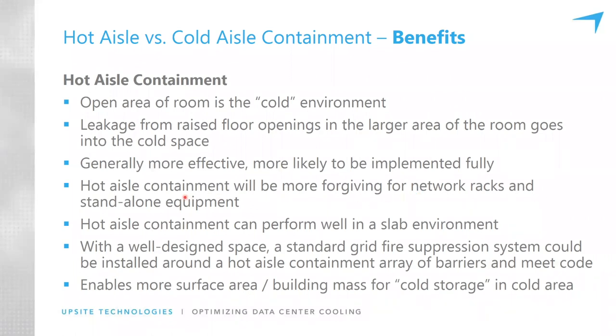Hot aisle containment can perform well in a slab environment. And with a well-designed space, a standard grid fire suppression system can be used and installed around a hot aisle containment and still meet code. This enables more surface area and building mass for cold storage in the cold area, because the bulk of the room is cool rather than the bulk of the room being kept in a hot state. So that creates more ride through in the event of a cooling failure.